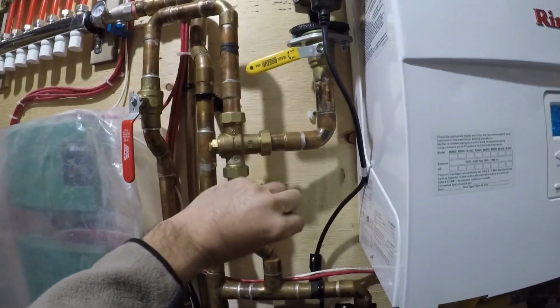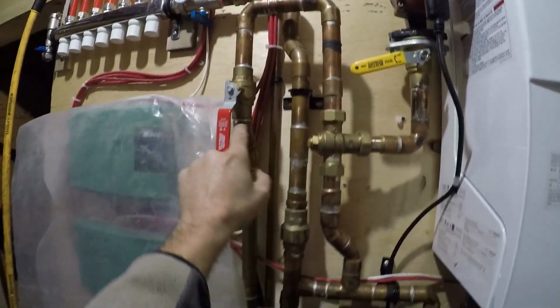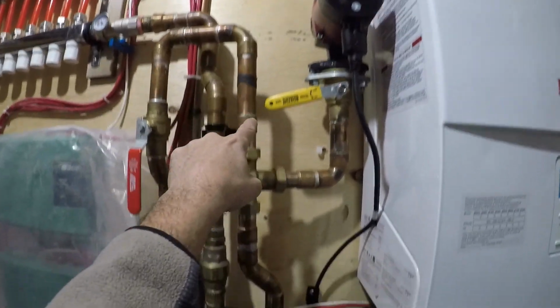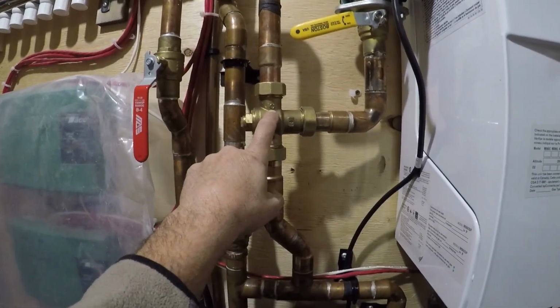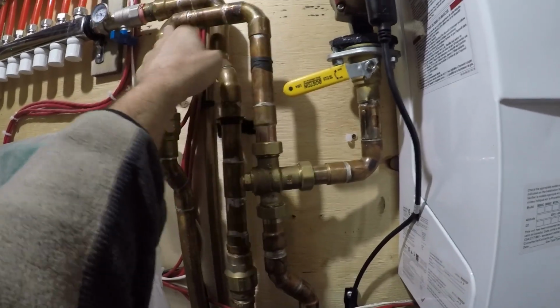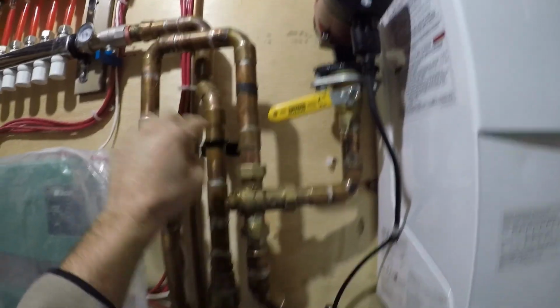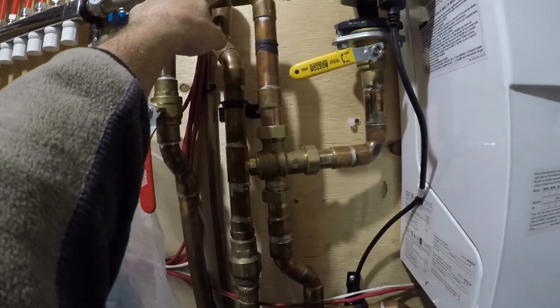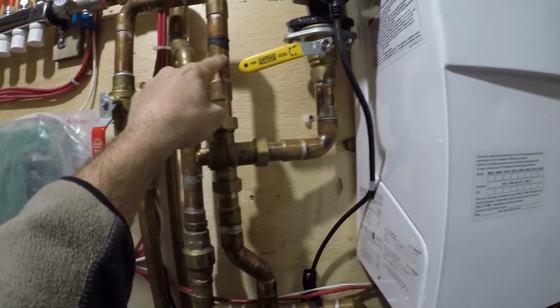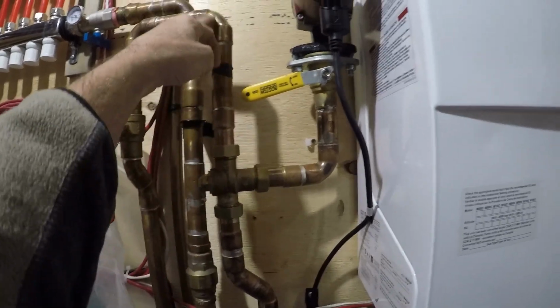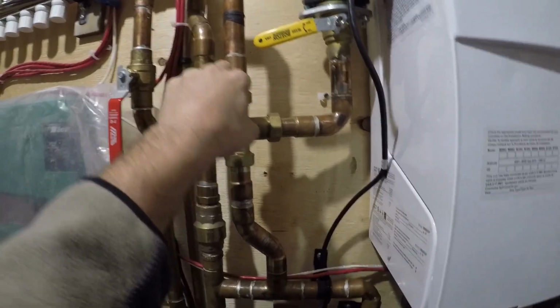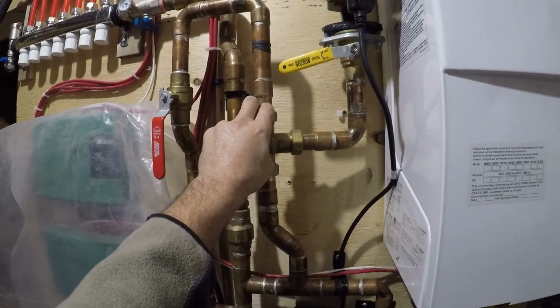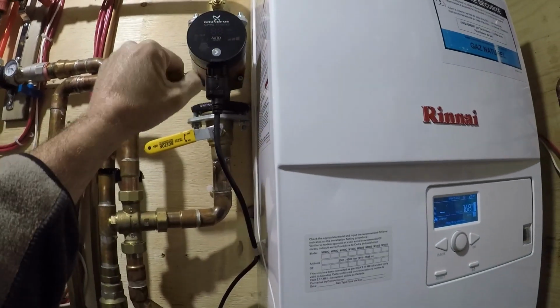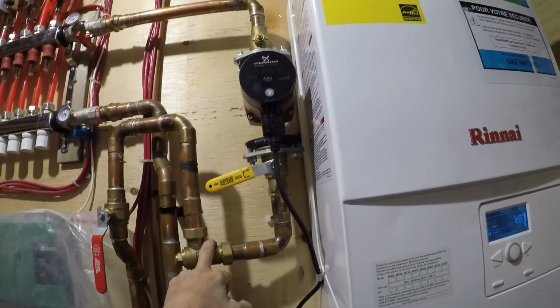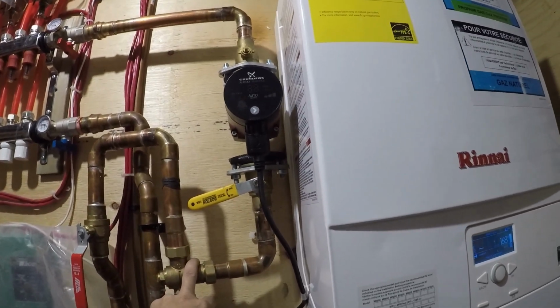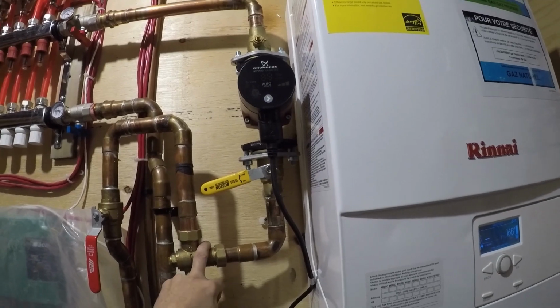The problem is, and I kind of wondered if it was going to happen when I did it, the way this cold water comes up and around, it doesn't seem to matter what I do, but it actually creates an airlock. So there's air stuck up in this pipe here, and it kind of makes sense because as you're flushing and filling the system, I can never seem to get this water out of here. You can always hear this trickling, which means it's not pulling in the cold water. In fact, I woke up last night and I could hear this pump, so I feel like this pump has air in it. So I'm really hoping it didn't get damaged by drawing air and not water through it. I hope it wasn't too long before I woke up.